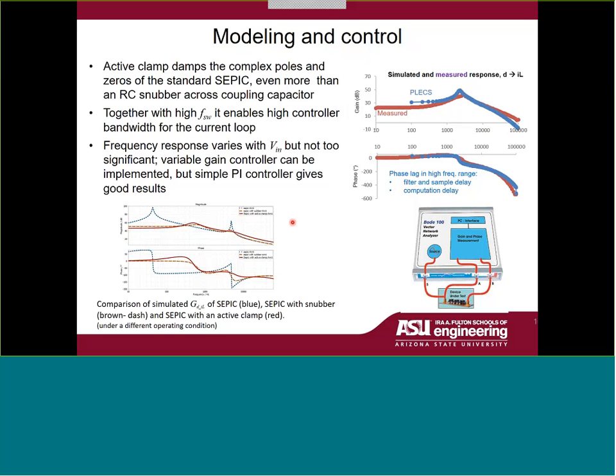These are some comparisons of the simulated frequency response and the measured response from a network analyzer. They show fairly good agreement, but more importantly, it's a much more benign transfer function to compensate. The gain does depend on input voltage, but not too significantly. So we could potentially use variable gain control, but our experience has shown that a simple PI controller gives very good results for the current loop, and that's what we're using currently.